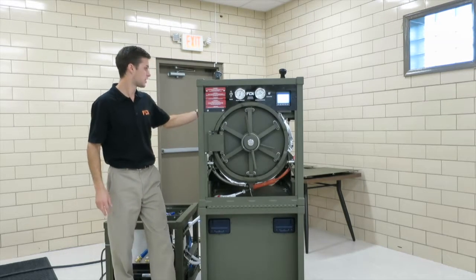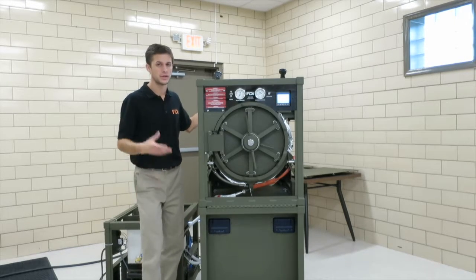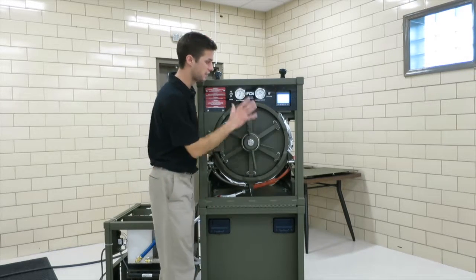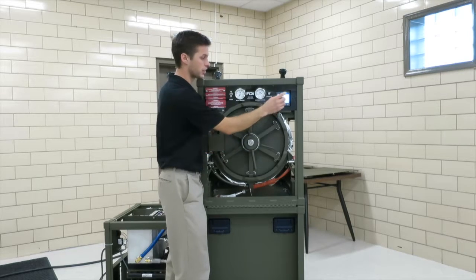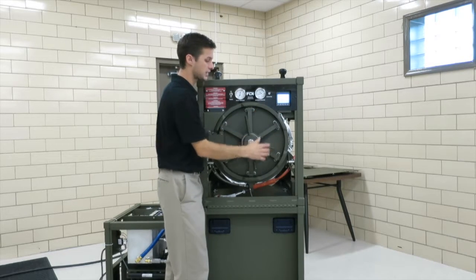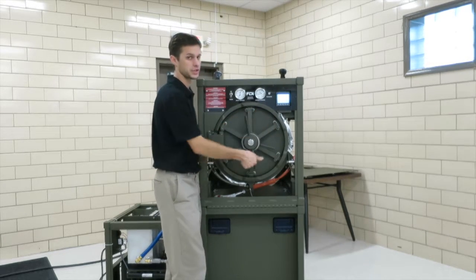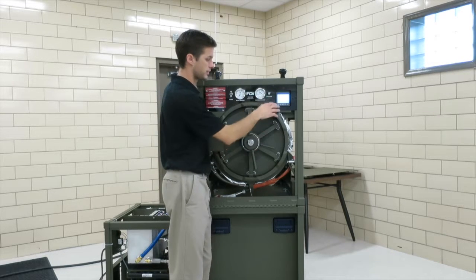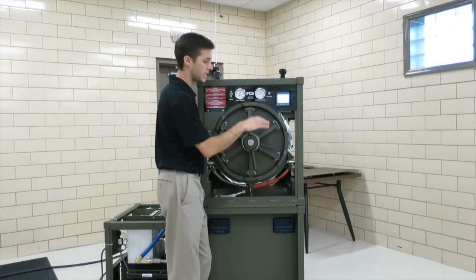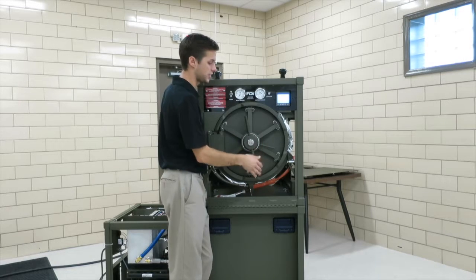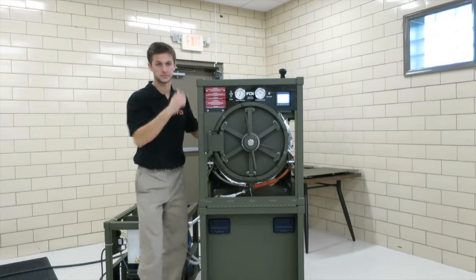So could have a clogged HEPA filter. If you're sitting at idle and you're not in a cycle and you press vent, if you don't tighten the door, you can also get this long vent time, because in order for it to vent, it has to pull a slight vacuum, and it can't pull a vacuum if this door is not tight.